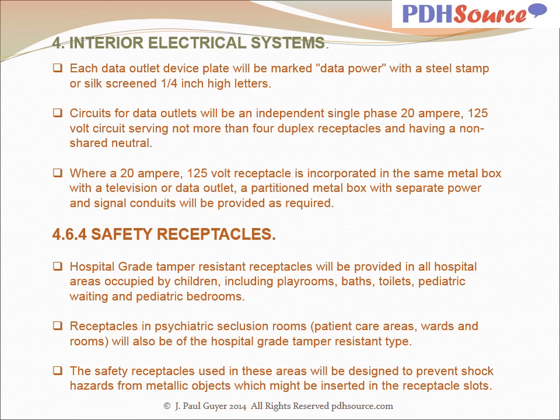Safety receptacles, hospital grade tamper resistant receptacles will be provided in all hospital areas occupied by children, including playrooms, baths, toilets, pediatric waiting, and pediatric bedrooms. Receptacles in psychiatric seclusion rooms, patient care areas, wards, and rooms will also be of the hospital grade tamper resistant type. The safety receptacles used in these areas will be designed to prevent shock hazards from metallic objects which might be inserted in the receptacle slots.